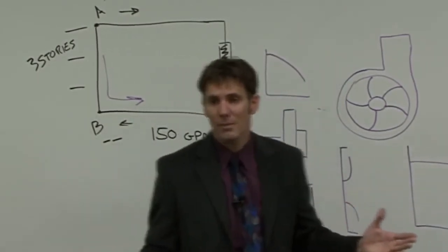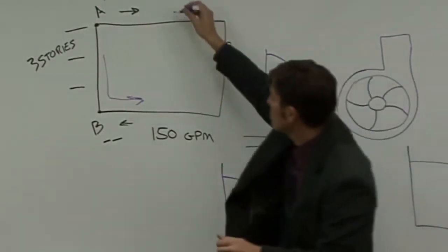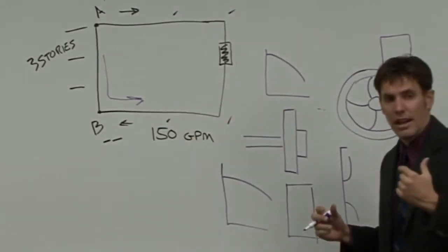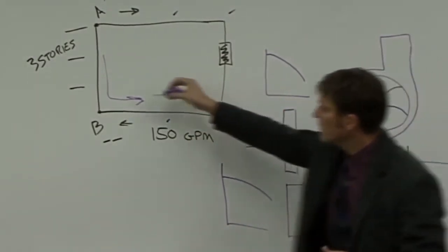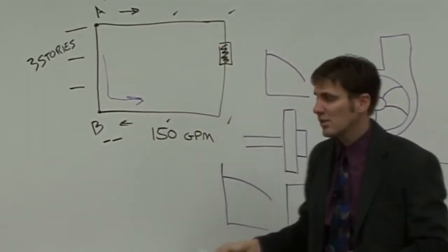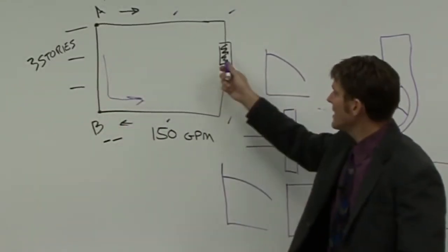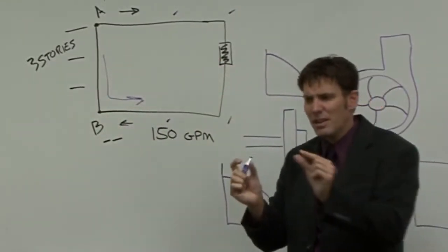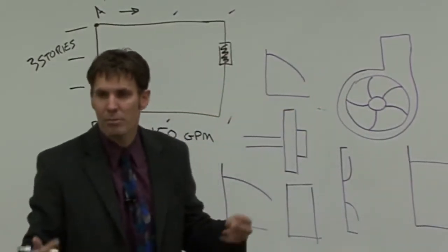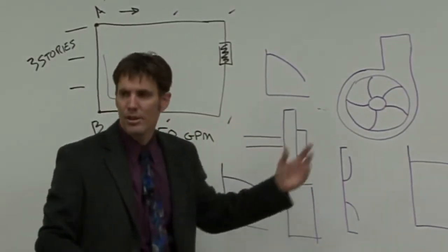I see engineers make a mistake when sizing their pumps or, as they calculate the pressure through the system. It's usually pretty standard in a closed-loop hydronic system. Because we don't have to lift the elevation, it doesn't matter how tall the building is. Really, it matters how long our piping is and how many zones we have. So typically, we're within a pretty good range. So all of your commercial HVAC pump manufacturers will have pumps that look fairly similar in their curves.